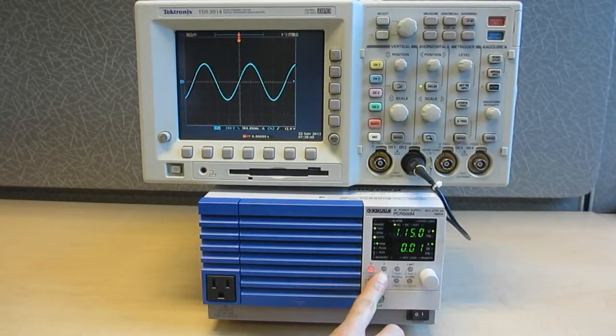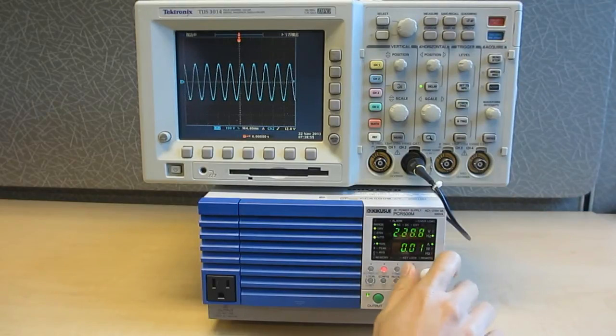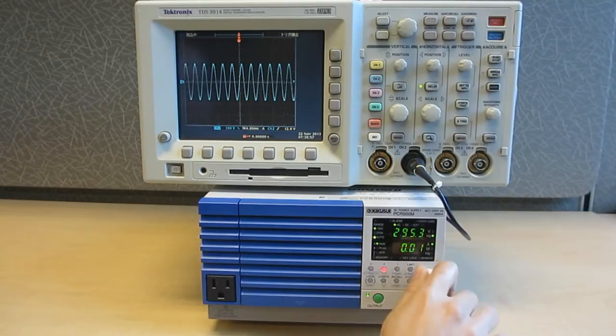Now we're going to show you the output voltage being set to 115V at 400Hz. As you can see, it's very easy to set the PCR-M for a variety of applications using the front panel.